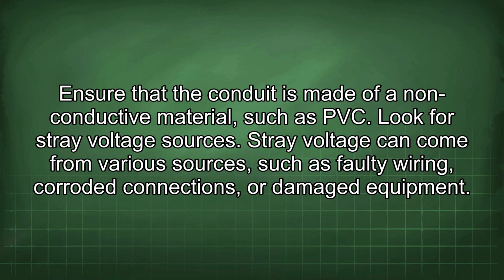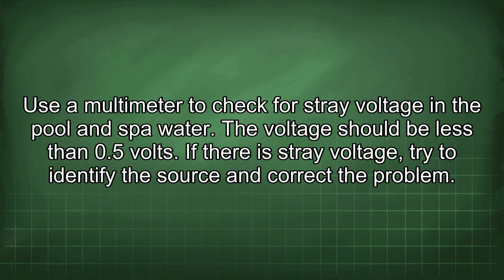Look for stray voltage sources. Stray voltage can come from various sources, such as faulty wiring, corroded connections, or damaged equipment. Use a multimeter to check for stray voltage in the pool and spa water. The voltage should be less than 0.5 volts. If there is stray voltage, try to identify the source and correct the problem.